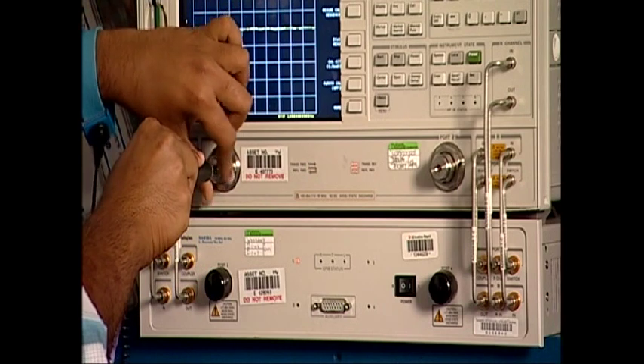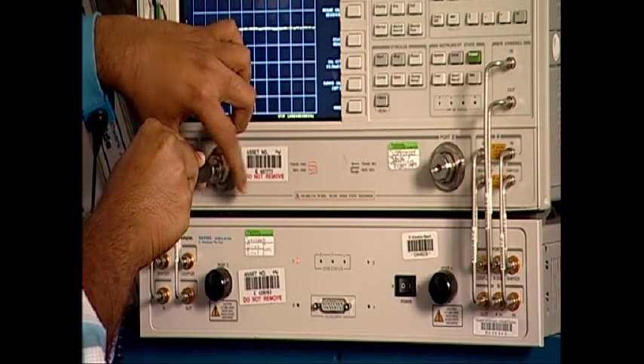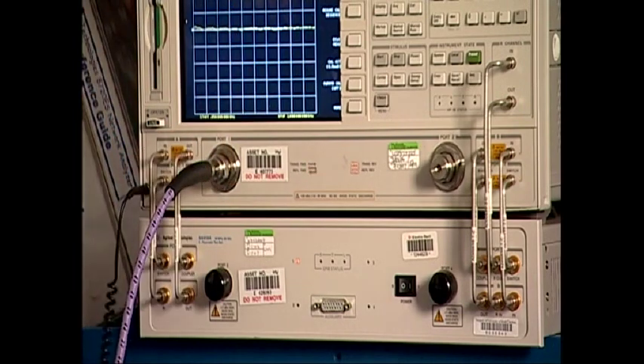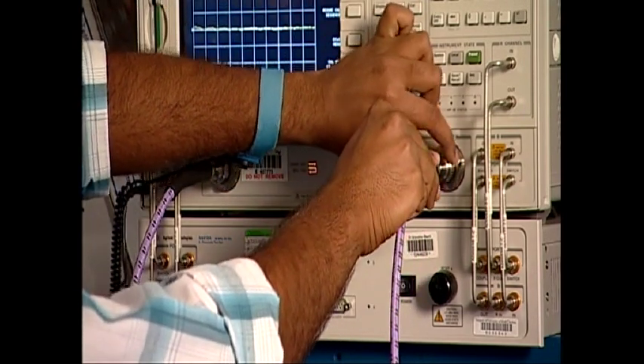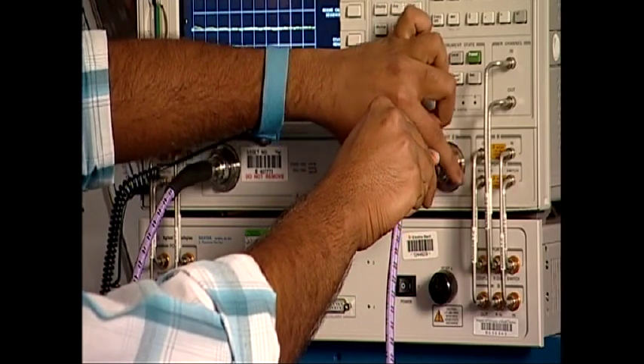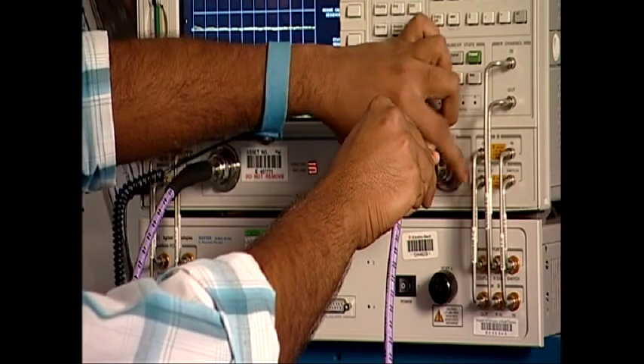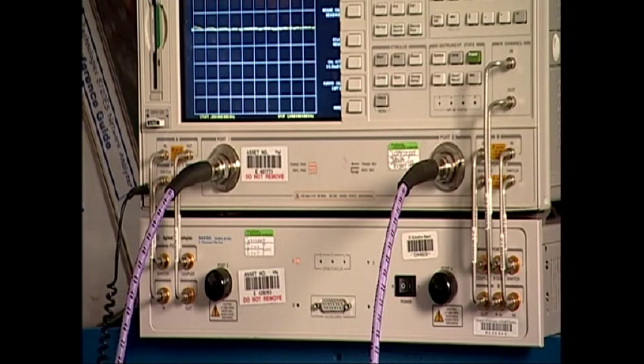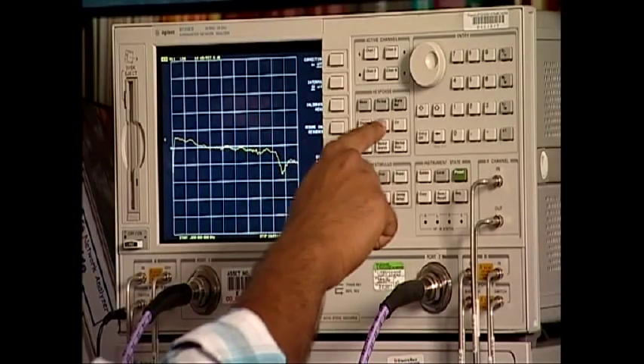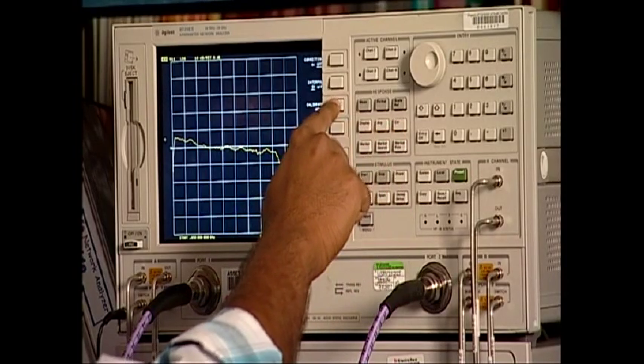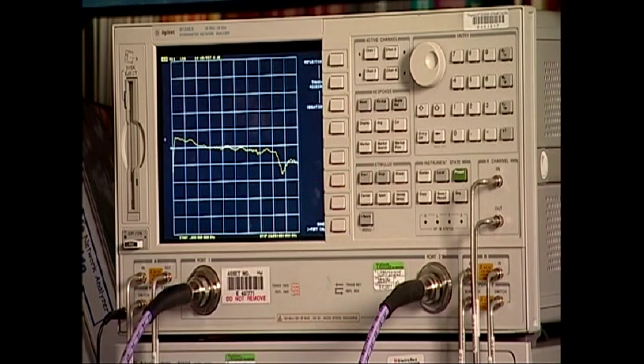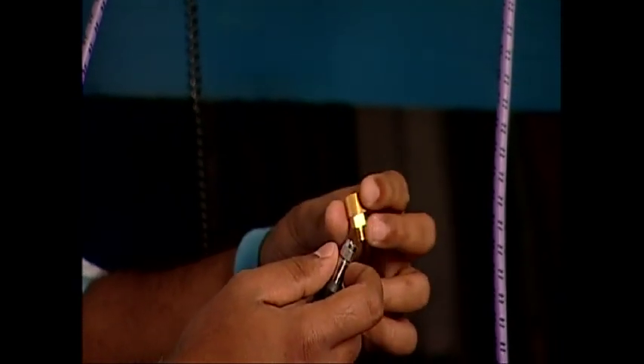For this, we'll have to connect the two cables at ports 1 and port 2. We then select Cal, Calibrate menu, full two-port. For the forward measurement, we use the cable that is connected at port 1. First, we connect the open standard to the cable at port 1.